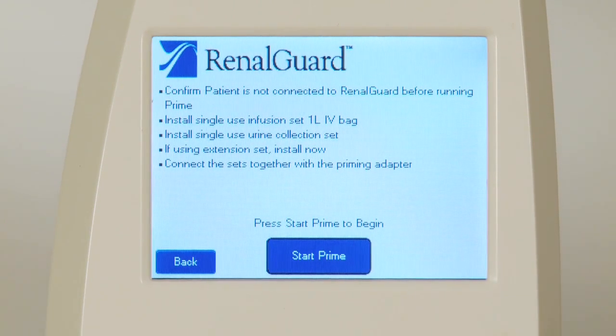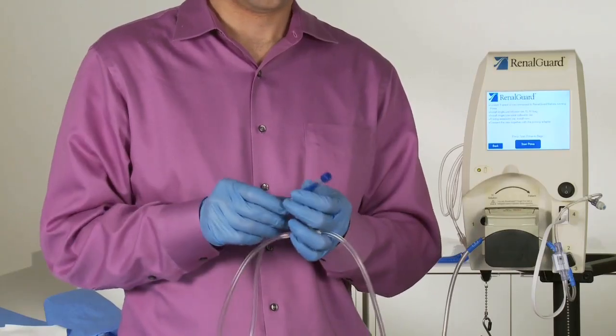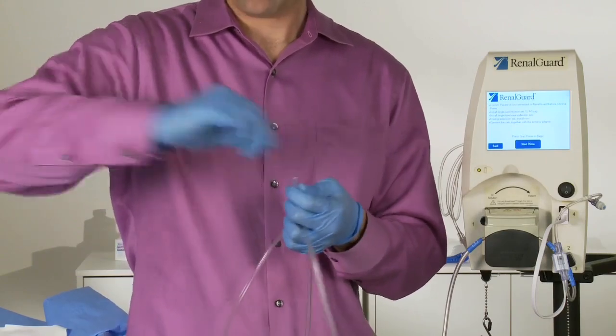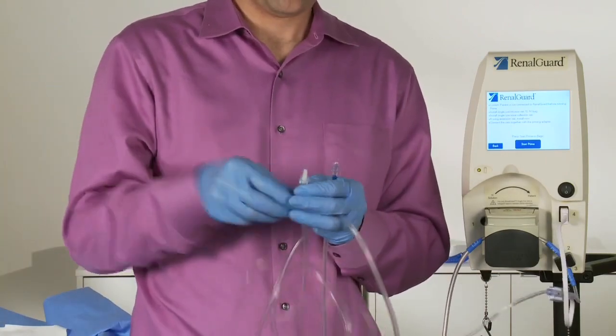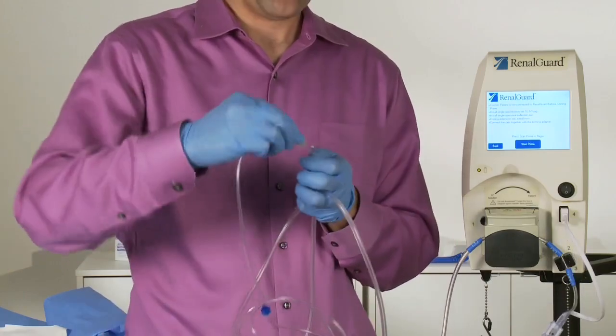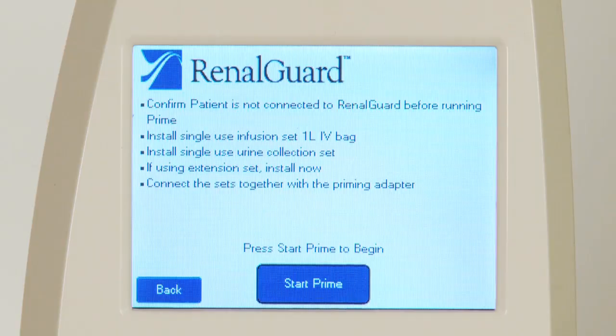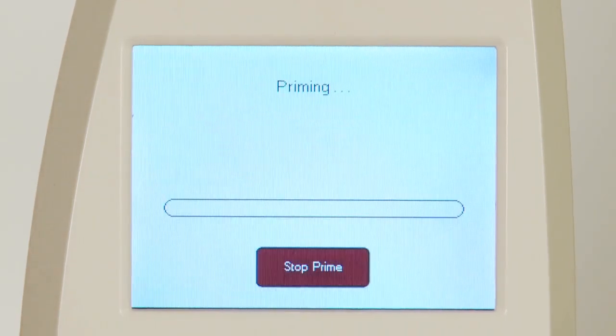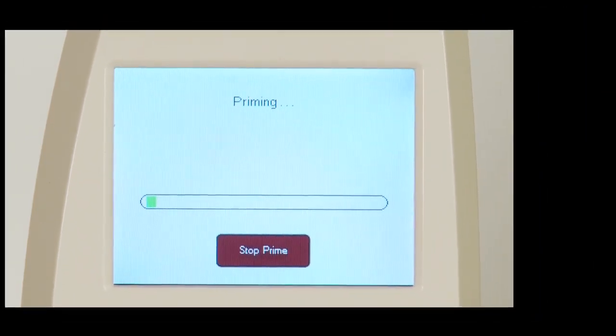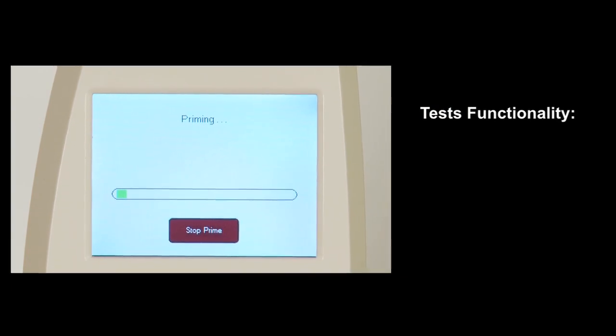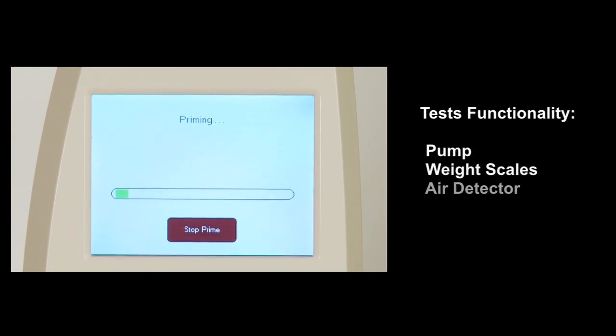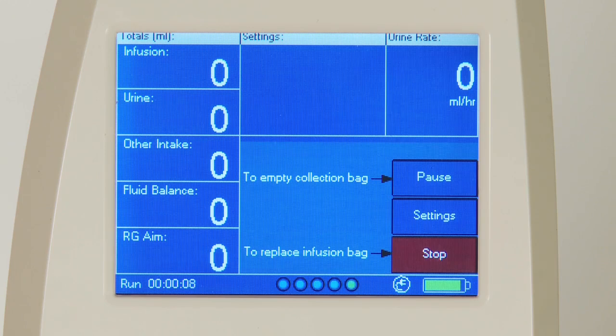Now we're going to prepare for priming the set. Take the cap off the priming adapter and take the cap off the infusion set and connect the two together. And press prime. Prime performs a number of important functions and takes about 2 minutes. Prime fills the infusion set and urine set with infusion fluid and tests all of the renal guard's functionality, including the pump, weight scales, air detector, and pressure sensor. Once prime passes and the pump stops, you will see the home screen.